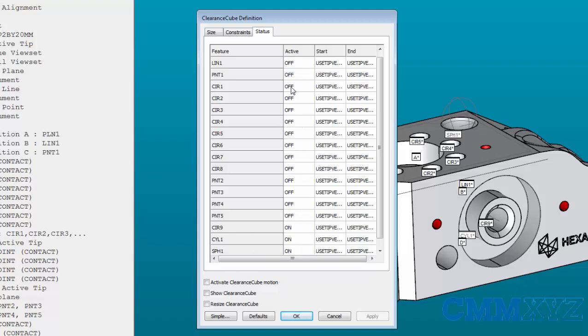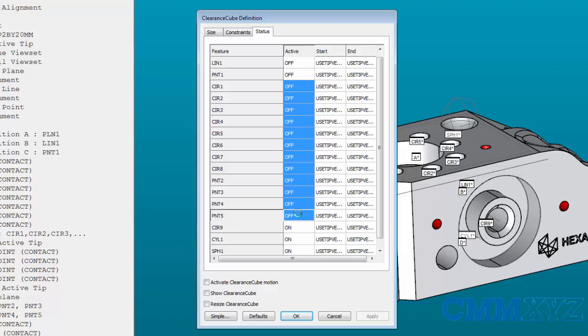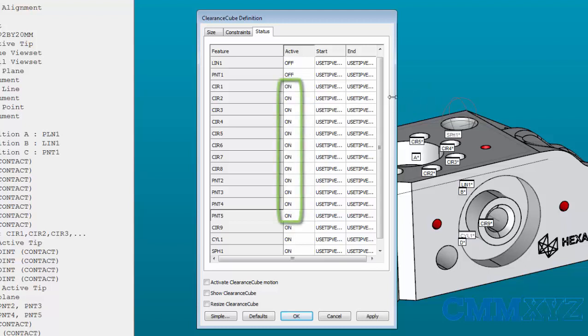I need to set these features to on, so then they could be used in the Clearance Cube for safety moves. The simplest way to do this is to grab your first feature after your manual alignment, click and hold the mouse, and drag down till you highlight all the remaining features that are set to off. When you release the mouse button, a menu pops up, giving me a choice under Active to turn it off or on. So if I click the On button, all these features now are set to on, meaning they will utilize the Clearance Cube for measurement.